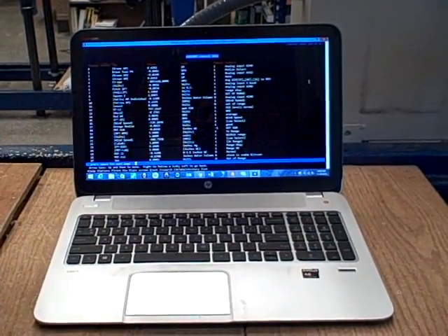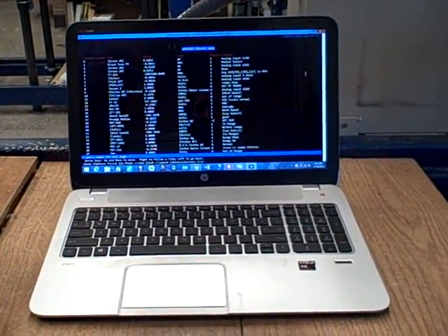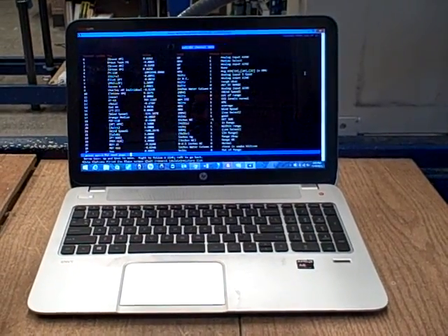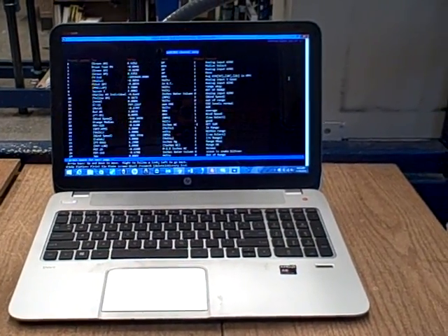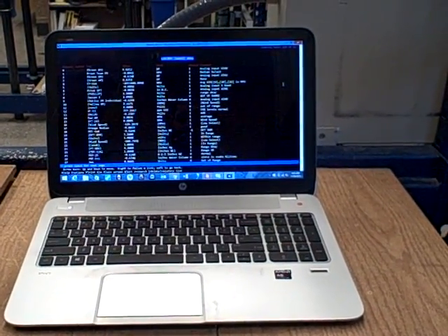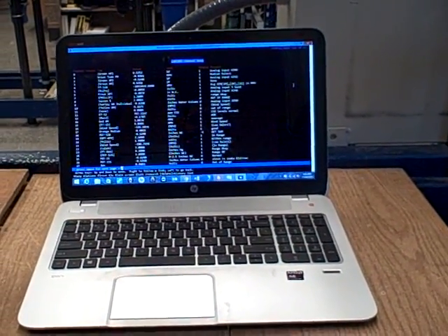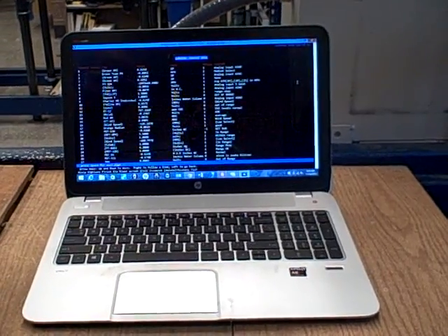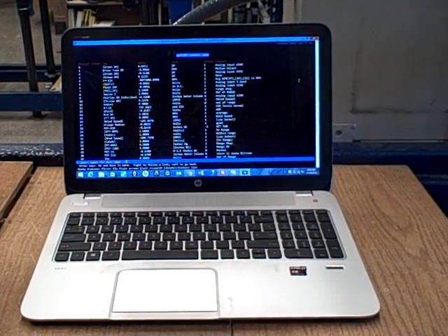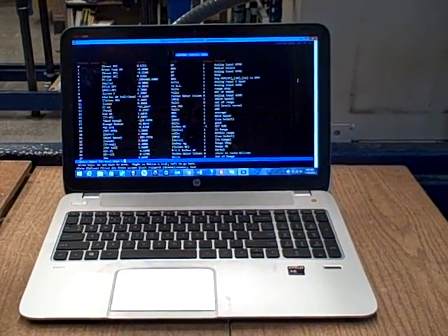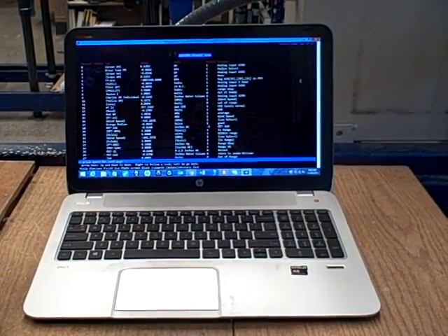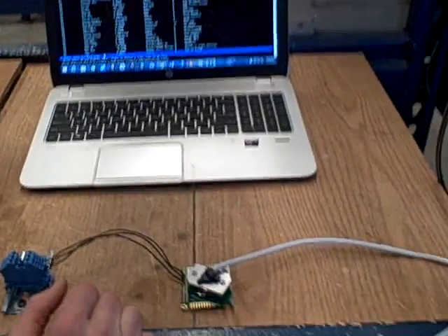Currently we're reading 797 parts per million CO2, which is above atmospheric. Atmospheric is about 400 ppm, and the reason it's above that is because I'm talking, and as I'm exhaling, we have carbon dioxide in the vicinity of the sensor, which gets picked up.